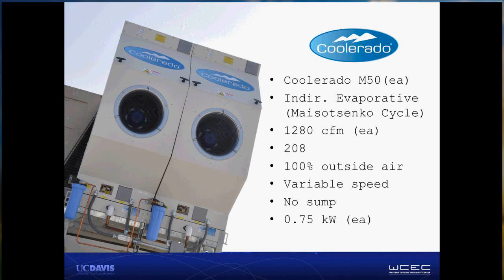So the first piece of equipment that we have installed there in Bakersfield is the Coolerado M50. This is an indirect evaporative system using Coolerado's unique Maisotsenko cycle. Each of the M50 units is about 1280 CFM, and in order to match the design requirements for this project, we paired them together, as you can see in this picture. The system's nice because it's modular. You can pair as many together as you need to make the airflow that you desire. So we applied 2 and added those on as a retrofit to the existing rooftop units.